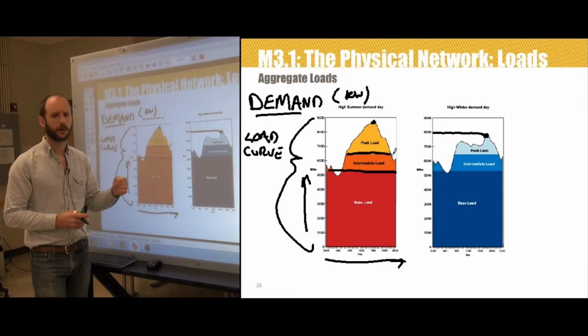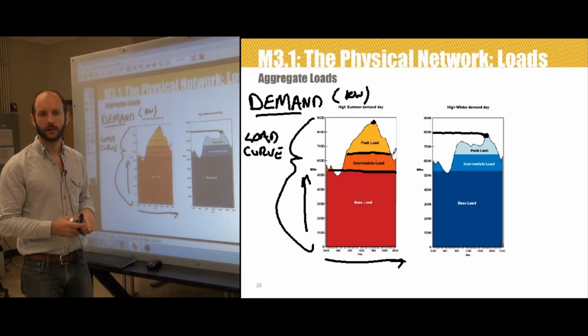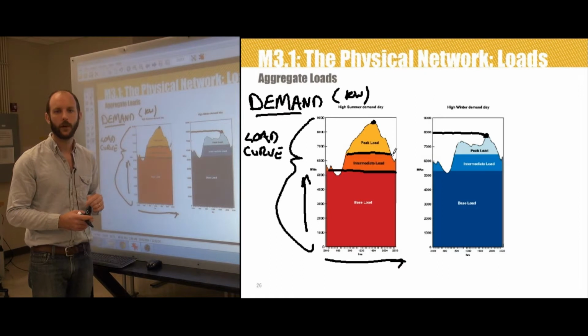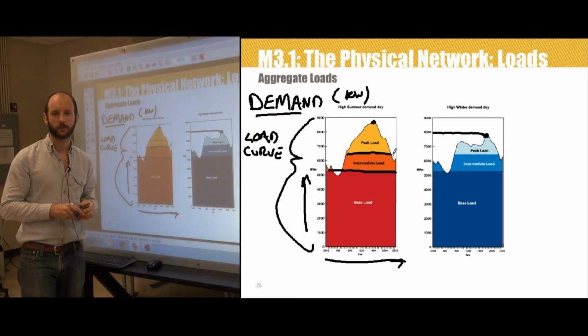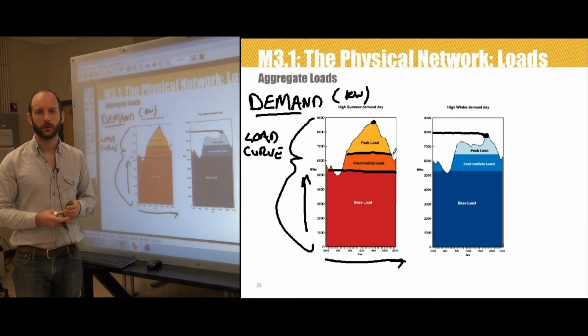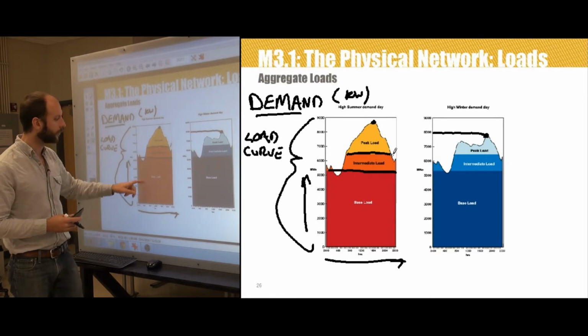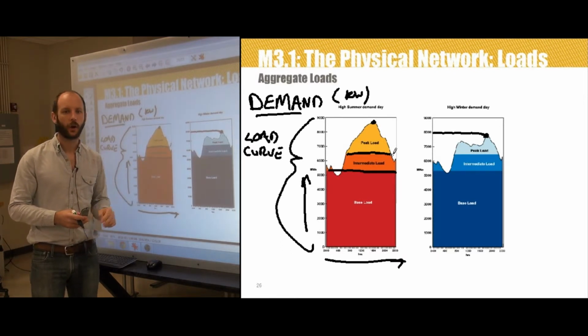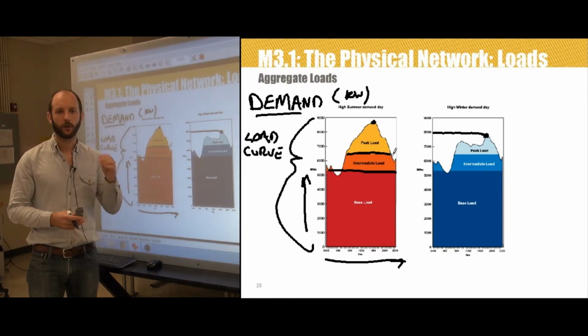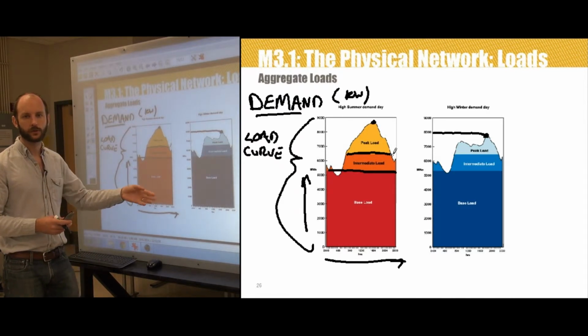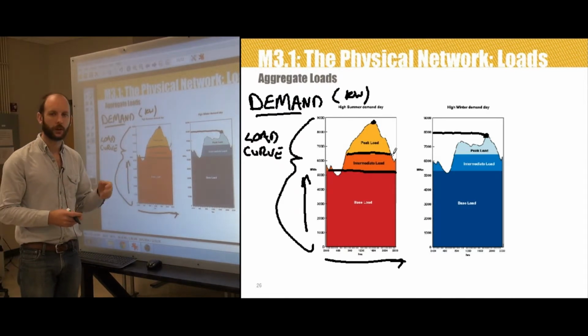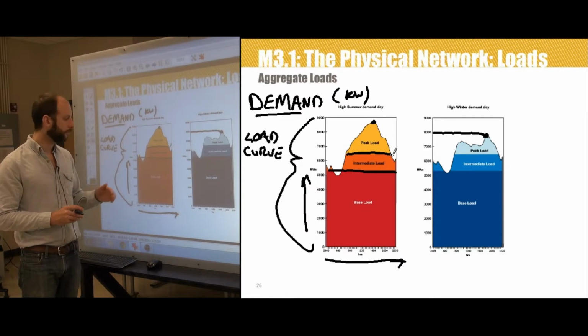The other way that this is met is sometimes we use load management techniques such as demand response, where we shut off HVAC systems for brief intervals to meet these loads. Notice that if you integrate this load curve, or add up all the area under the curve, you would get the total energy consumed by the load, or the aggregate load in this case.